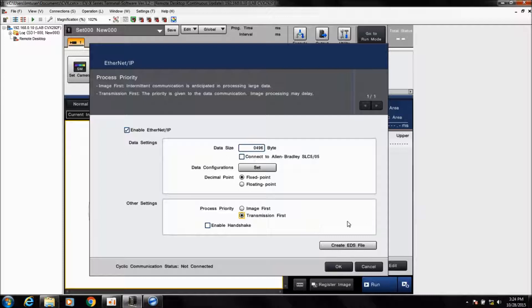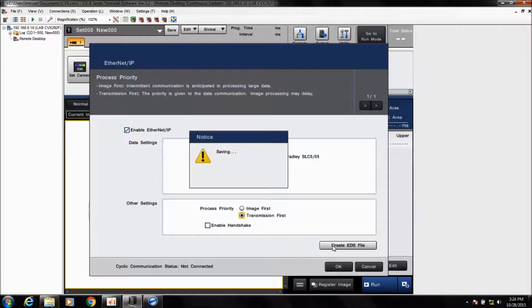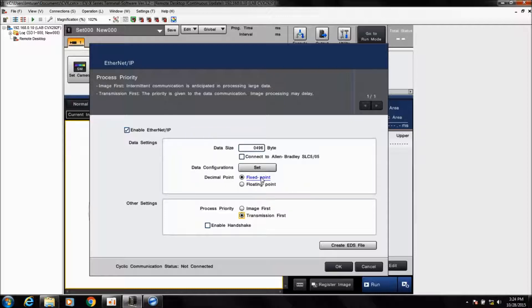In the same menu you can create the EDS file. If you're doing this directly on the controller, click this button and it will save to an SD card. It will create an EDS folder inside the CVX folder containing the EDS file needed to import into the Allen Bradley software. You can also do this via the CVX Vision Simulator software — come to the same menu, click the same button, and it will create the file to the workspace.